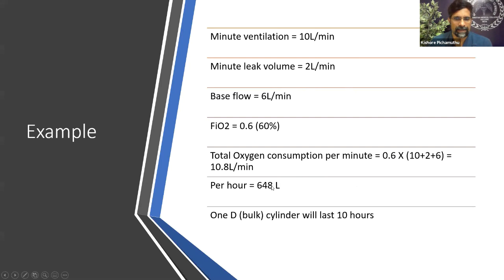And then you can of course calculate in terms of cylinder numbers how much this would last. Now of course you must remember that this is just a rule of thumb calculation in the sense that it depends on different ventilators. Like Dr. Vijay Anand mentioned, some devices that are gas pressure driven will use some of the oxygen pressure to drive the ventilator. There's some older ventilators sometimes, or certain transport ventilators, that do this, and therefore they will consume much more oxygen. Turbine-based ventilators, these are the more recent ventilators.